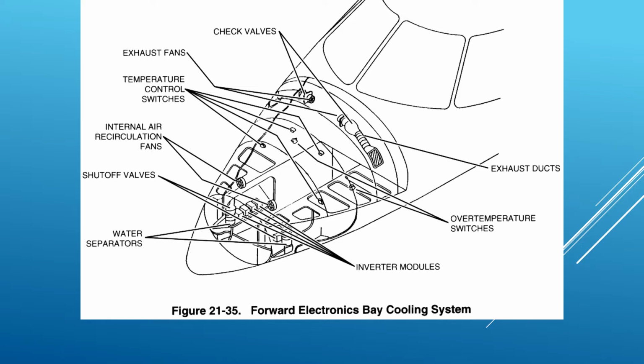So inside the E-bay, you've got a series of 4 control switches and 2 over temperature switches. So the 4 temperature control switches control the exhaust fans. So you have 2 switches per fan. Any one switch in its pair that goes above 24 degrees C will cause the exhaust fan to come on. So it is quite possible, although not usual, to have 1 exhaust fan running and not the other one. But from my experience, one single exhaust fan will start, and I can guarantee you within a minute or so the second one will also kick in. So they do work individually, but they will both be running nearly all the time.